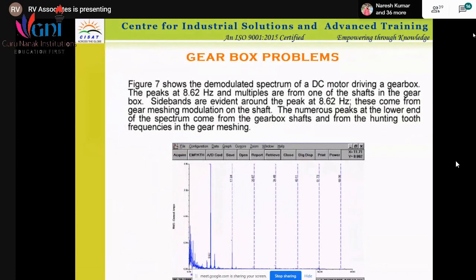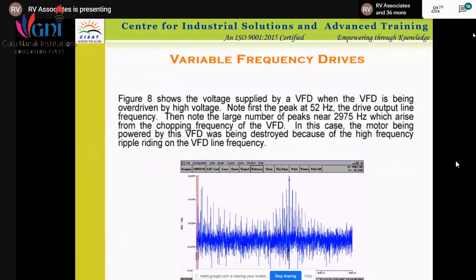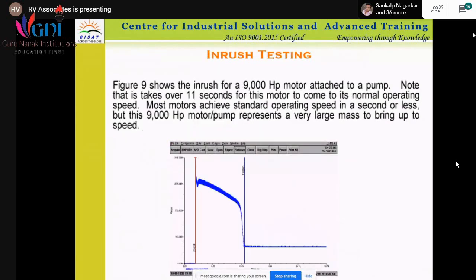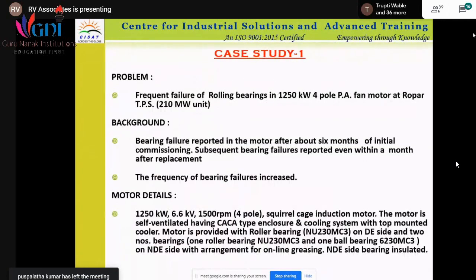Then there is a gearbox problem. So this is how the pattern will be for gearbox failure. Variable frequency drive: if you are using a drive with the motor, then the pattern will be different. There may be some changes in the frequency, and there may be changes in the harmonics. That has been completely analyzed. Inrush testing for the motor: how much current is there, and that rise in the input current. So these are all the various case studies for the motor.